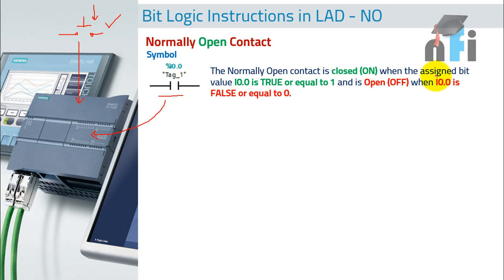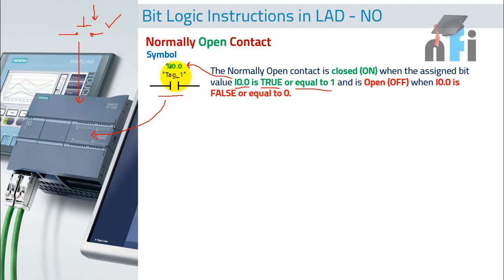This contact goes on when the assigned bit, the value I0.0 — this is the address. This goes through as true, meaning it closes when I0.0 is true or equal to one. And this bit is open or off when the address I0.0 is false or equal to zero. This address is either true or false, and it depends upon the switch or the signal which is connected to this input.